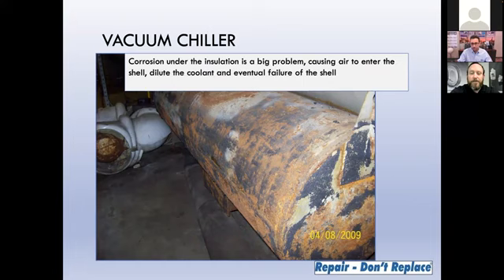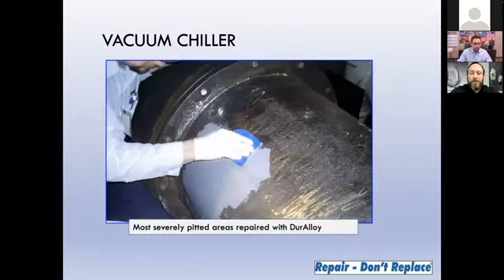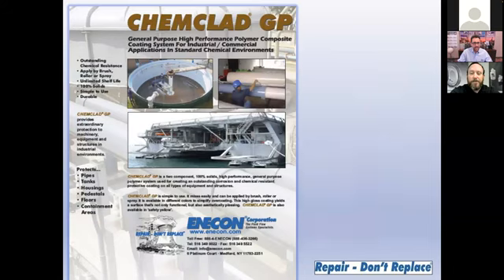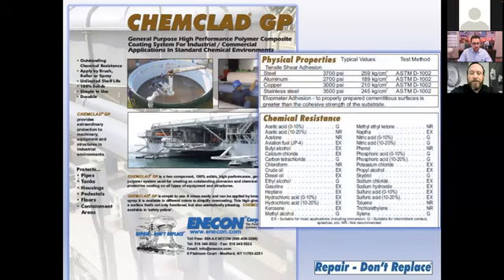Abrasive blasting or mechanical prep is the first thing that we do to start the process of completing this repair. We'll then rebuild the most severely pitted areas with Duralloy and apply 2 coats of ENECON's ChemClad GP to all surfaces. ENECON's ChemClad GP is the product of choice. It exhibits outstanding adhesion and provides the corrosion protection that we're looking for on this exterior application prior to reinstalling the insulation on top.